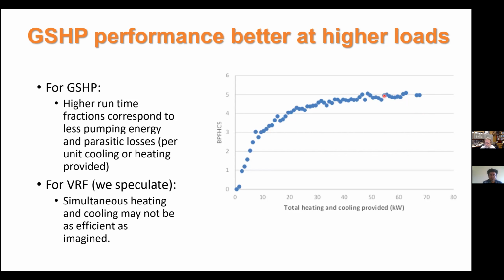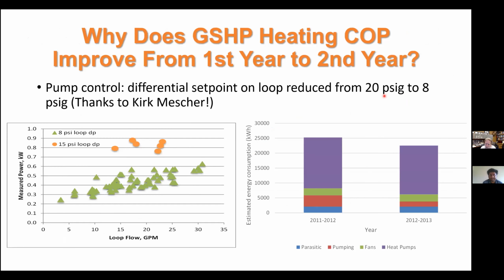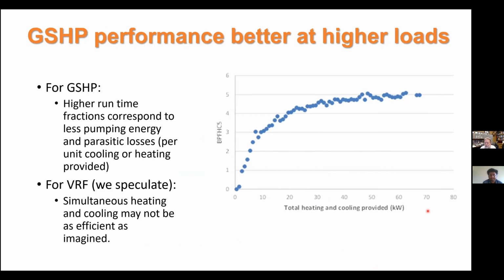And it flattens out as we get to a relatively high runtime fraction. If we go back a few slides, there was this blue here, which I'm calling a parasitic load. The pump controller uses some watts of electricity even when the pump's not running. The heat pumps use a very small amount of electricity, 10 or 12 watts or something like that, when they're not running. And those factors come in. Then for the ground source heat pump system, the fans run all day, even when there's no cooling or heating being provided. So those things tend to make the overall system performance drop as we get to lower load conditions.